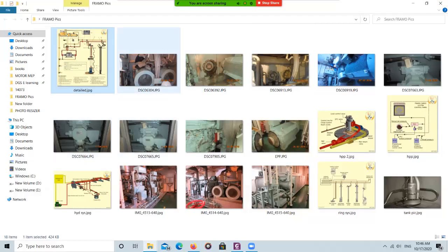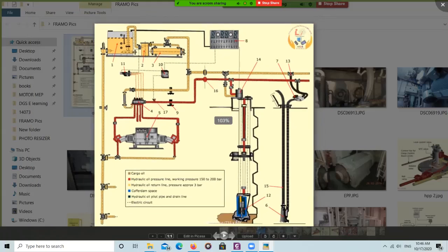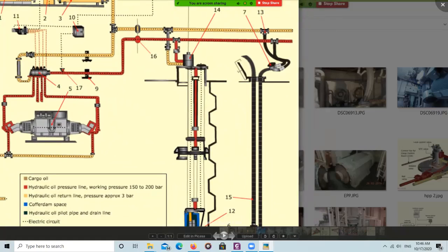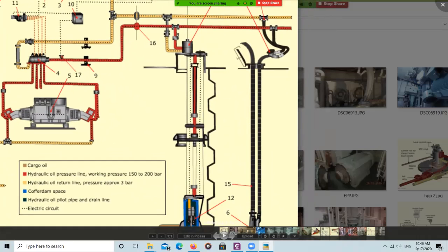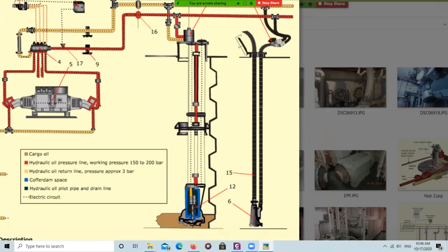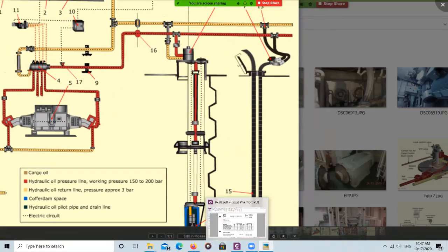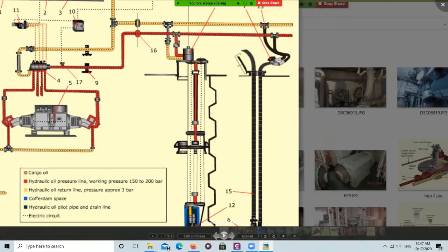There will be snap couplings and designated ports on the walls to attach them for operation of the portable Framo pump. An opening on the tank dome is used, through which a tripod is placed. One person must stand by to lower the portable Framo pump inside the tank, and as discharging proceeds, he has to lower the pump further inside the tank to ensure positive suction is always maintained.